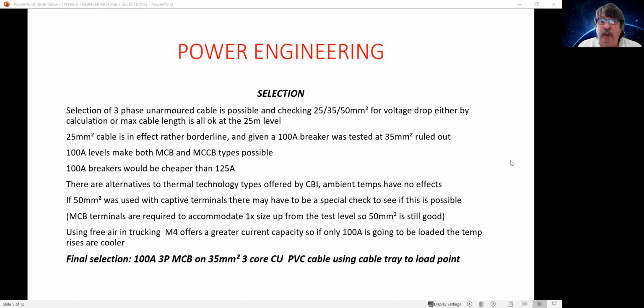So here we have an opportunity to go with a 100 amp circuit breaker. The cheapest option would be the 100 rather than the 125. A miniature type would definitely be cheaper than most brands of the more industrial molded case type. And if we had to use 50mm cable, it all fits. Of course, there are alternatives, and there are companies like CBI which offer ambient temperature non-effect type breakers, which are not affected by temperature due to their technology. They're a non-thermal technology type, hydraulic magnetic in this case, which would also offer some benefit.